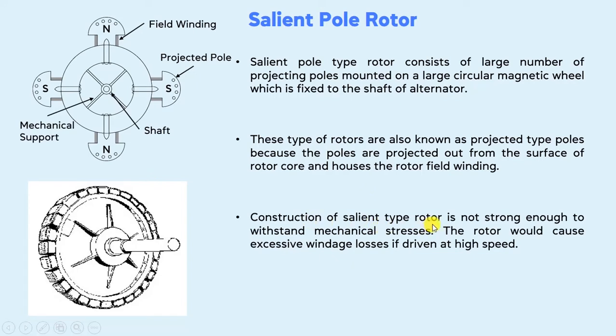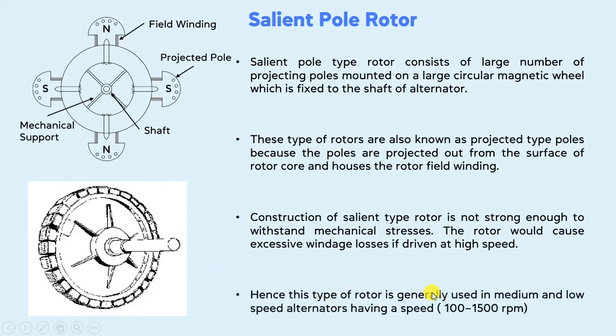The construction of salient pole type rotor is not strong enough to withstand mechanical stresses. If a salient type rotor runs at a higher speed, the outer poles — also known as projected type poles — experience a high centripetal force, due to which the poles of the rotor tend to fly apart. This would result in excessive windage noise. For that reason, this type of rotor is only used in medium and low speed alternators having a speed of 100 to 1500 RPM, since it cannot be run at a higher speed.